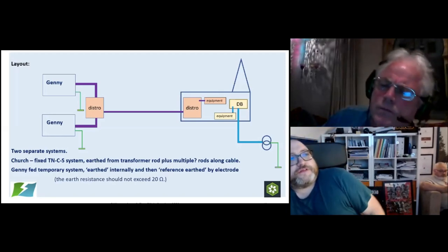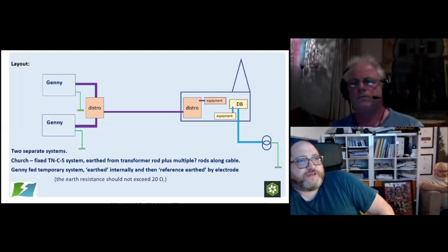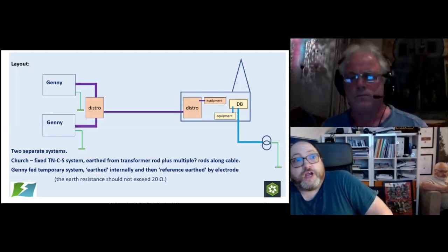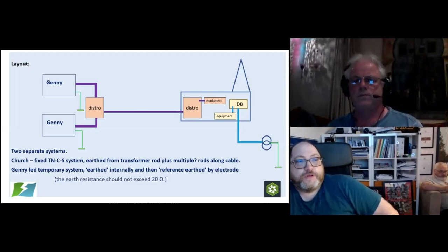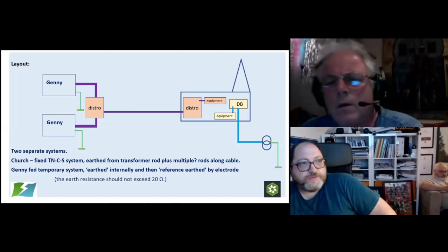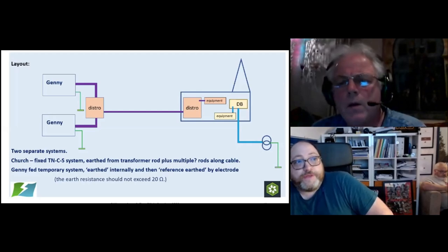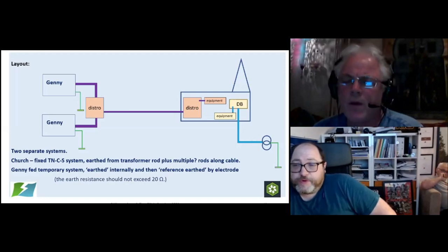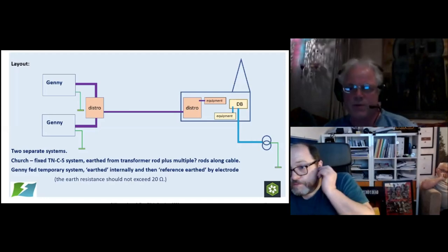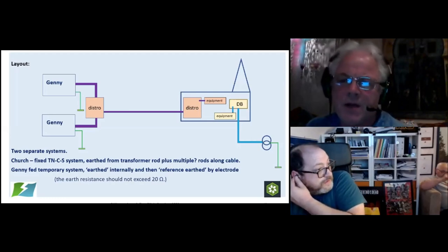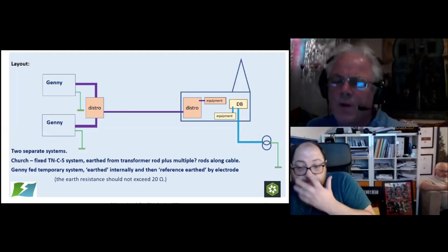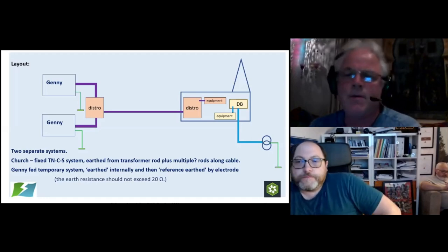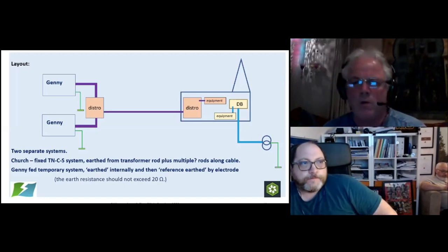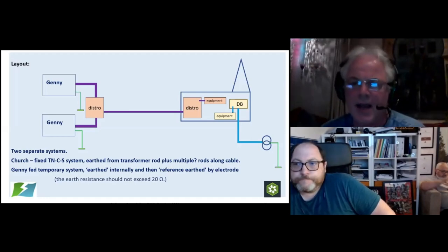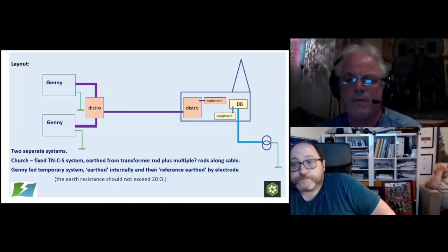Do installation methods and controls mitigate shock risk? So we're asking you to allow more or longer current flow on temporary systems. So if we do adjust our systems, is our design or our method mitigating any shock risk? Or if there's a risk of shock, is it just instantaneous disconnection at that point? Most electrical faults are from equipment, which is obviously plugged in and added to the system, which is on an FDU. All final circuits must be protected by a 30 milliamp RCBO or RCD. That's instantaneous, and every final circuit feeding a piece of equipment must be protected by that.